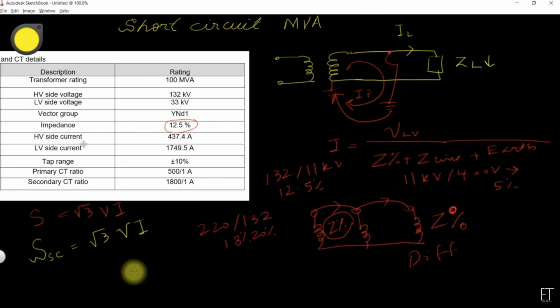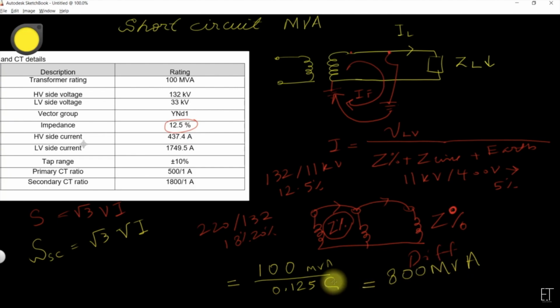So how do you find the short circuit MVA of a transformer? The formula is quite simple. You divide the MVA of the transformer, which is 100 MVA, by the percentage impedance divided by 100, which is 0.125. So the short circuit MVA is 100 divided by 0.125, which comes to 800 MVA. So you can see here, this is 800 MVA, the short circuit MVA of a transformer.